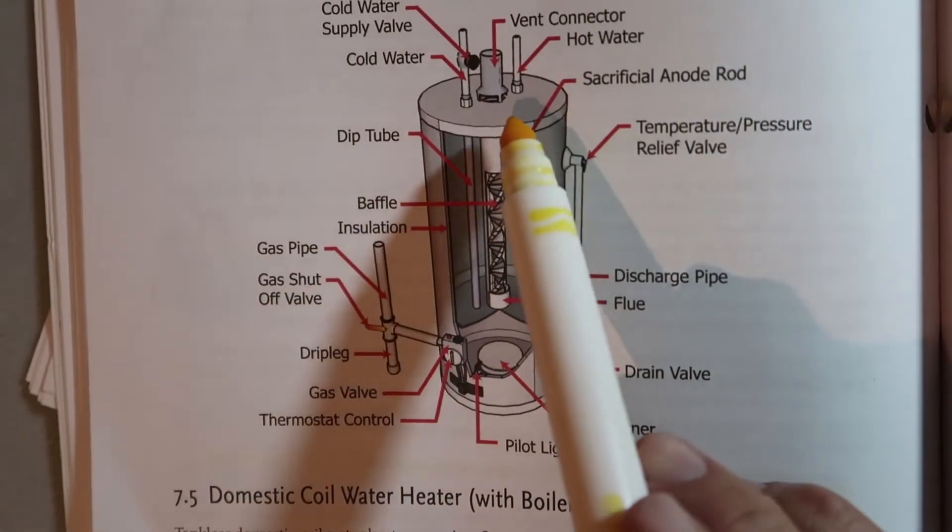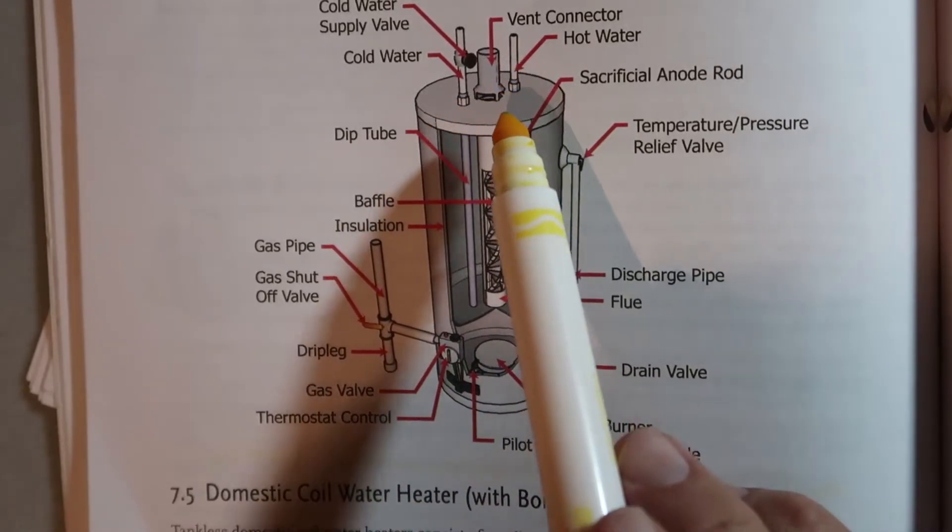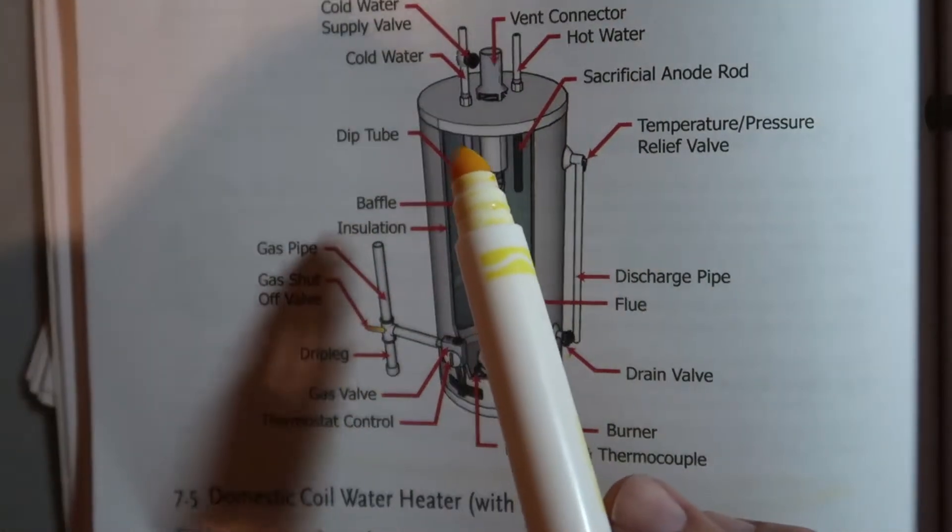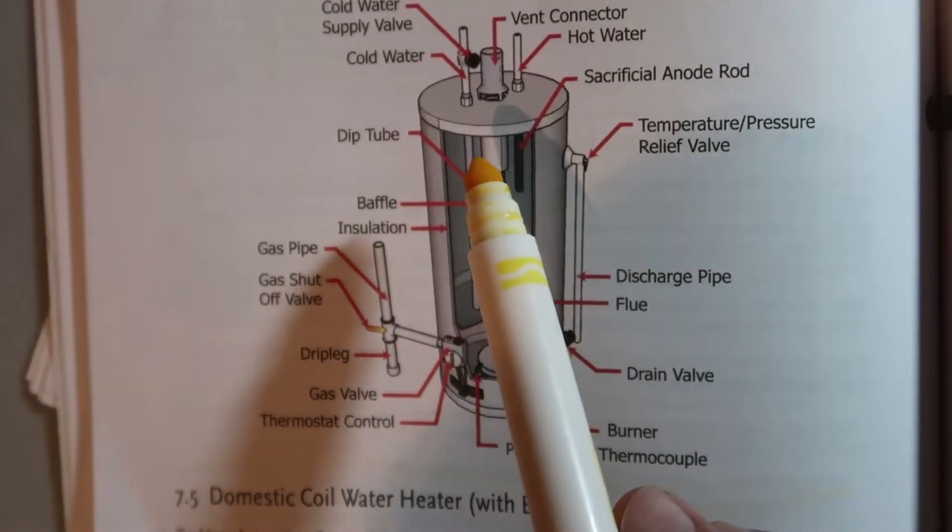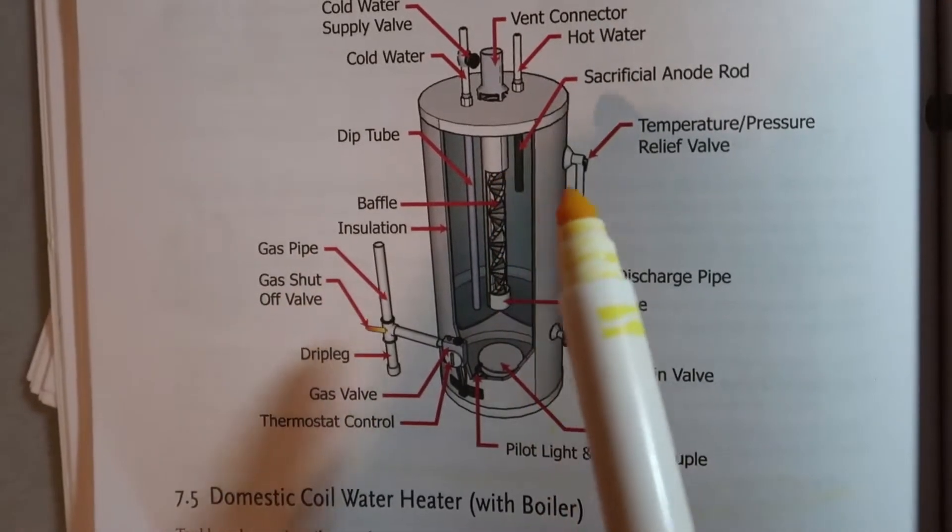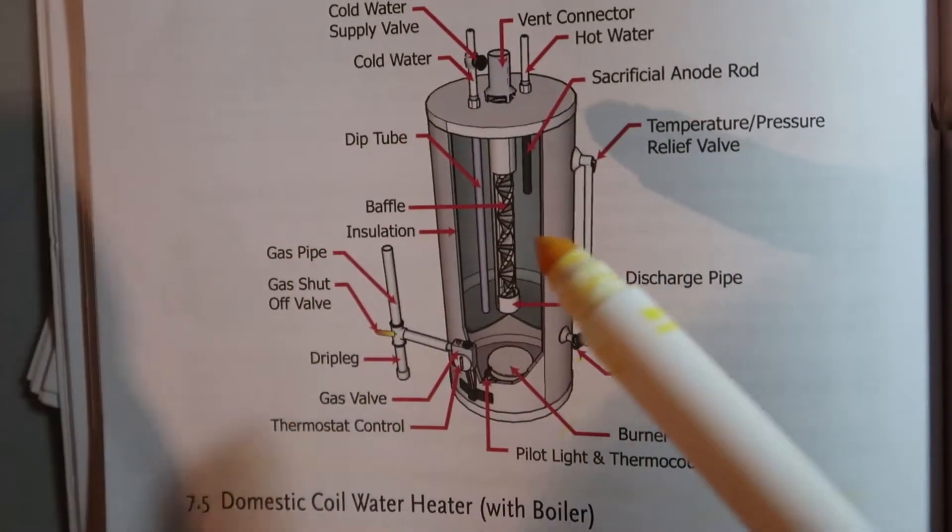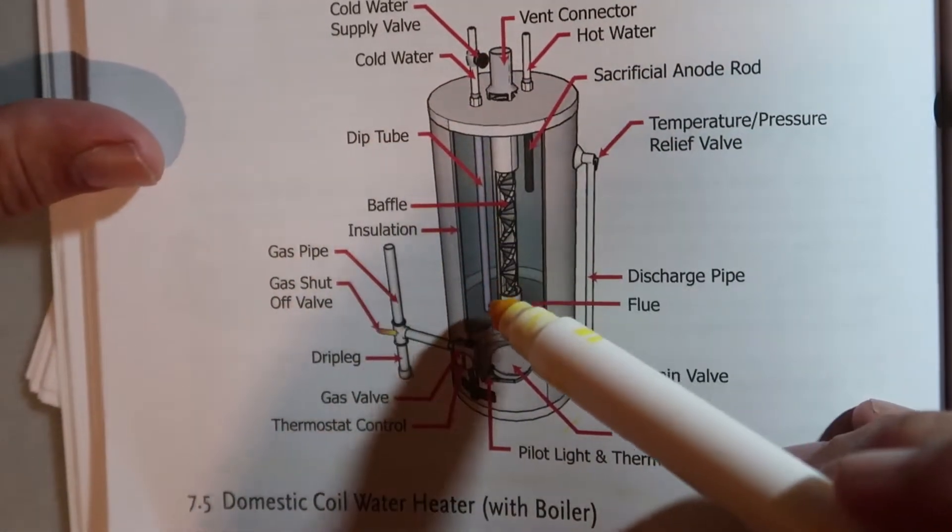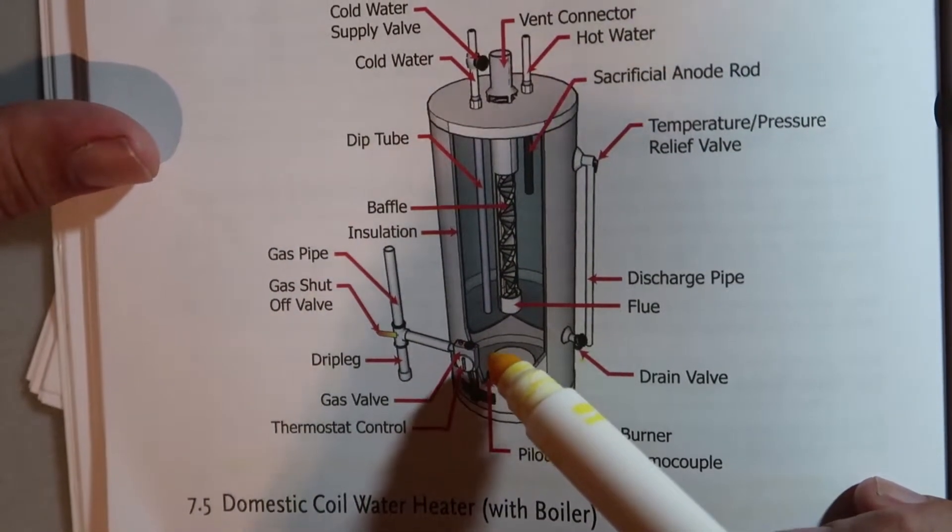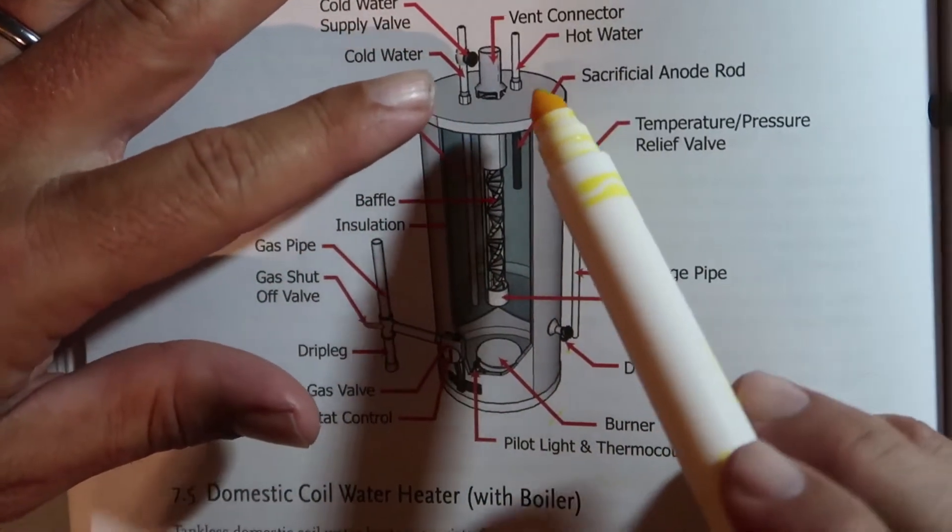You're going to look for any corrosion here, look for any deposits or soot around the draft hood or the vent connector, so that something may not be venting quite as well or there could be some back drafting there or something restricting the flue. That's a telltale sign. And you obviously have your cold water coming in where this tube goes all the way in, because you want the cold water down at the bottom of the water heater because as it warms up the warmer water is going to rise.